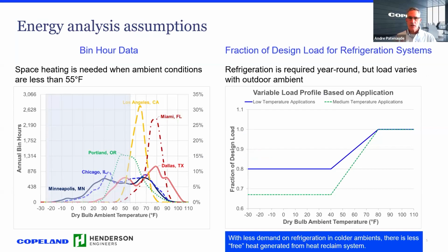So for the sake of the study and the energy analysis assumptions, we have to look at the bin hours of operation of all those 6 climate zones, of course, and how many hours they operate at every temperature in the temperature bins. And we decided to use 55 degrees and below as the point of ambient temperature that required heat. Now you may be sitting there and say, yeah, but my stores need heat at up to 70 or 75 degrees, but we couldn't have a moving target. So we decided 55 was the point where everything below 55 dry bulb ambient required heat, and above did not. So that was our line.